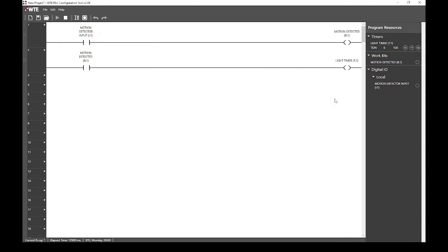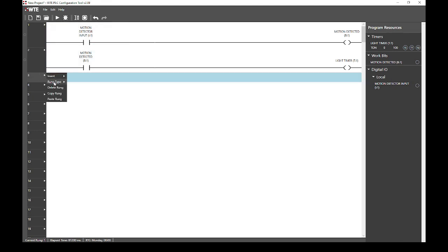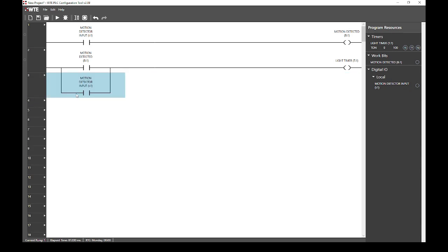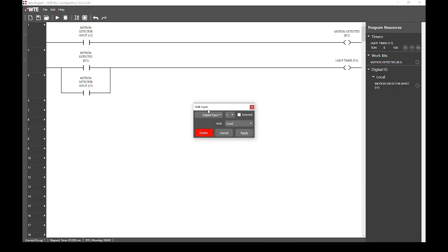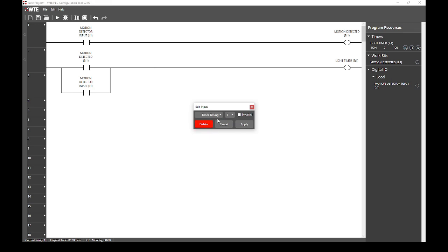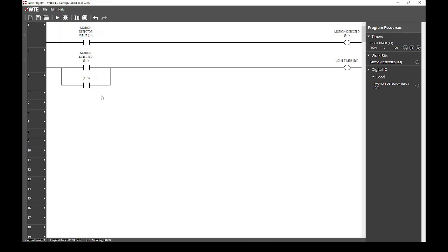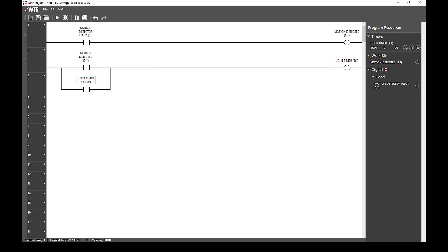We start by creating a new branch below rung 2. We do this by selecting the rung menu for rung 3 and changing the rung type to a branch. Be sure to stop the program before you continue. We now want to change this branch input from the default input 1 to the timer 1 timing flag. This flag is only active while timer 1 is counting up. It is not active when timer 1 is finished. We will rename this flag to give it a descriptive name, such as light timer timing.